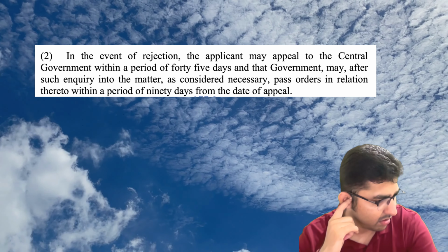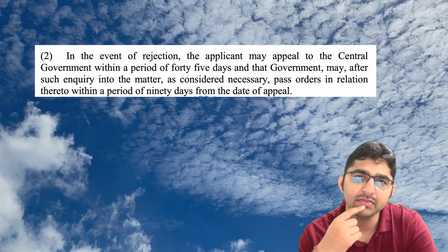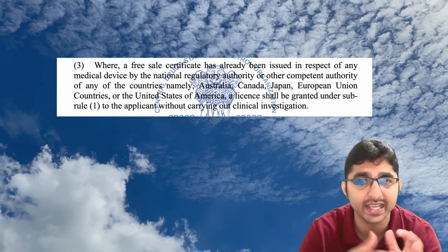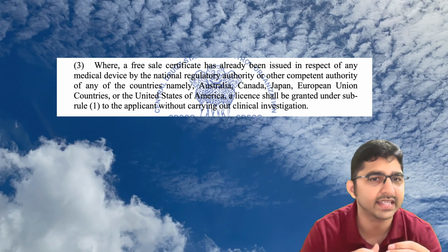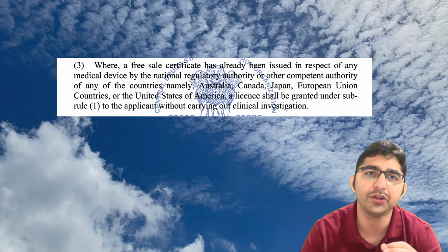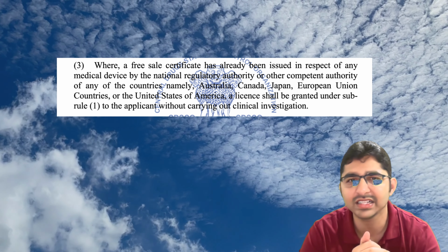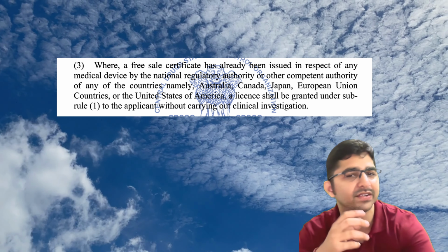However, your import license may get on a fast track by the CDSCO with the free sale certificate. If the medical device which you are going to import from the overseas manufacturer has already had the free sale certificate from a trusted regulatory authority like Australia, Canada, Japan, the European countries or the USA, then you can get the import license without clinical investigation in India. So this is very interesting, my friends, right?